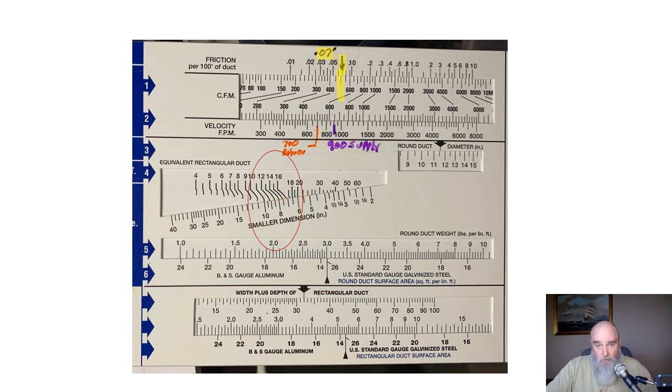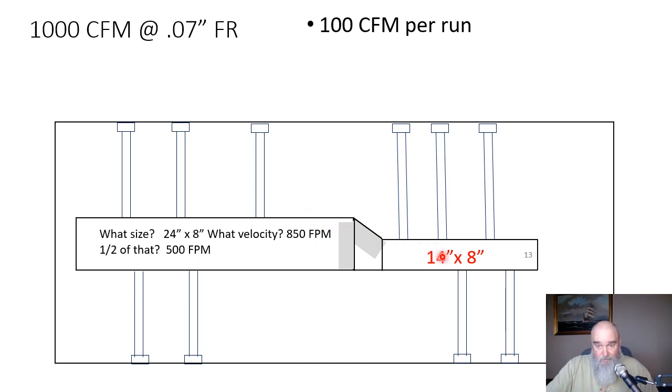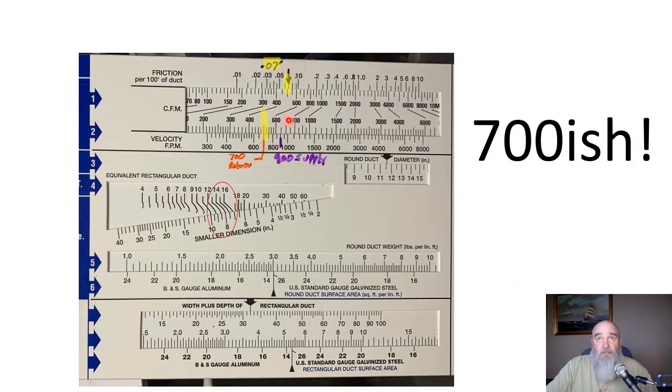So I got 14 by 8. How fast is it moving? It being that remaining 500 CFM. Grab the duct slide again and I might be off by a skosh but I don't care, it's close enough for me. I have my 500 CFM and it's lining up with about 700 or 700-ish in a piece of 14 by 8 ductwork. That's how you reduce your trunk.